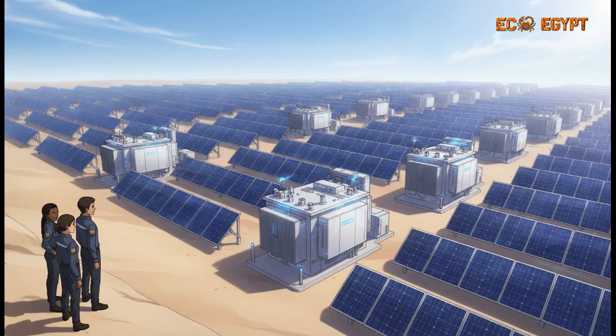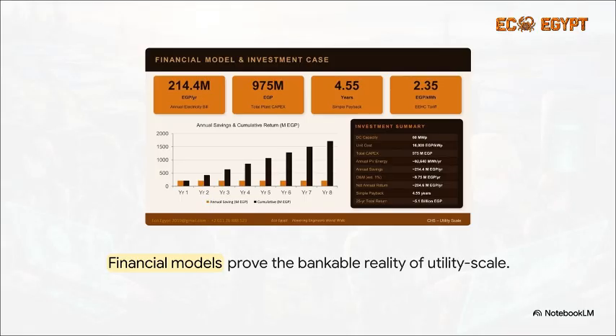We're dealing with 60 megawatts of peak DC capacity, which translates to about 50.4 megawatts AC. All that power is flowing through 168 massive Huawei inverters and 6 individual transformer stations, and it's spread across roughly 287,000 square meters. To put that in perspective, that is way larger than most residential neighborhoods. And to safely manage and route every drop of that energy, the site relies on a heavy-duty 12-cell 33 kilovolt MV switchgear system. But here's the thing about utility-scale engineering.